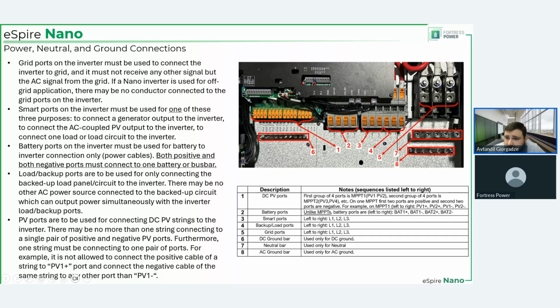Then you have number 5. These are your grid inputs. You have L1, L2, and L3 here, as I was saying, here and on L1, L2, and L3, and here on smart ports L1, L2, and L3. Phase rotation matters. It matters a ton. And you check for both smart ports and for the grid. And this is where your grid connects. Then number 7, you have neutral bar, and number 8, you have ground bar, right? Okay.